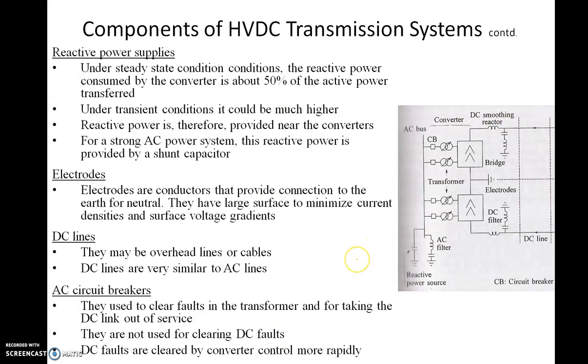Reactive power supplies are also essential. Under steady-state conditions, the reactive power consumed by the converter is about 50% of the active power transferred. So if you are transferring 100 MW, 50 MVAR of reactive power would be used — which is a huge value. Under transient conditions it could be even higher. This reactive power is provided by a shunt capacitor connected in parallel.